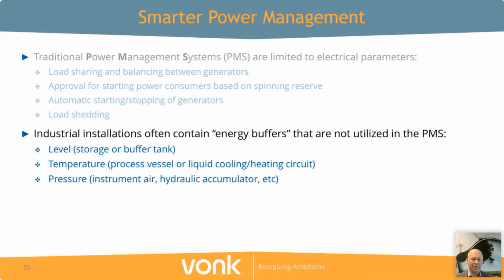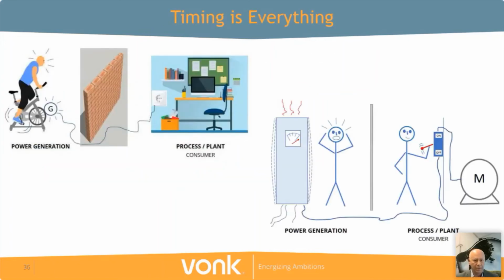It all depends on timing. Timing is very important here. I can illustrate this with these two pictures. The top left shows power generation going like mad—there's power available, but at the process side they don't actually need it at that moment. So there's no communication between process control and your power management system. There's, let's say, a virtual wall in between. This is not ideal, because when power is available, you could use it to bring that volume or pressure to a higher level.